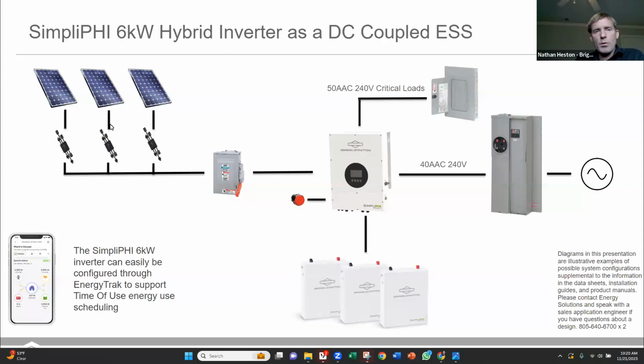And so I have this DC power coming out of my solar panels when solar is available, coming into a hybrid inverter. A nice aspect of a hybrid inverter is it's got the charge controllers built in. The Briggs Stratton inverter has 2 of those built in. That power is then directed into the batteries. And once those batteries are full, or once we're in a time of use period where we want to discharge those batteries, they can be discharged to loads. If there's additional power in addition to what is charging the batteries, that power from the solar is then directed to the loads as well. And if the loads are fully met and the batteries are charged and you have additional power available, it can be fed back out to the grid.